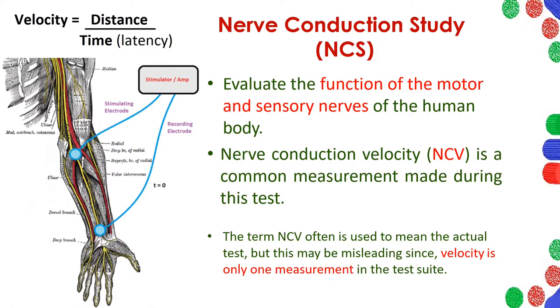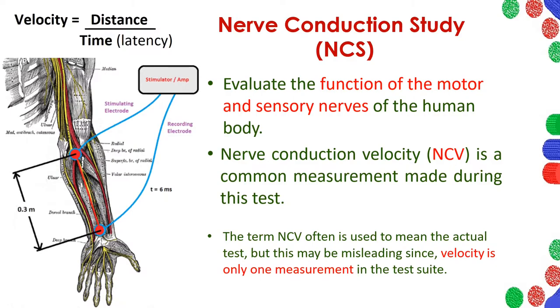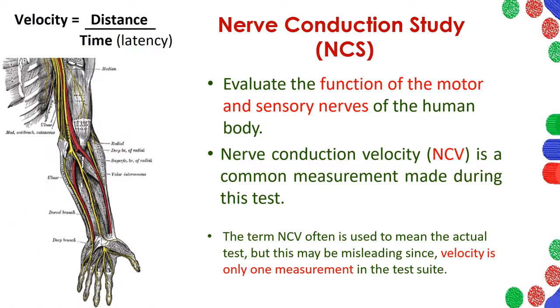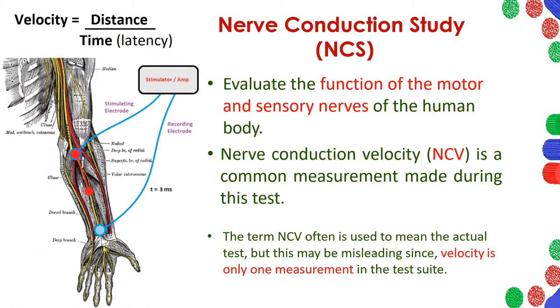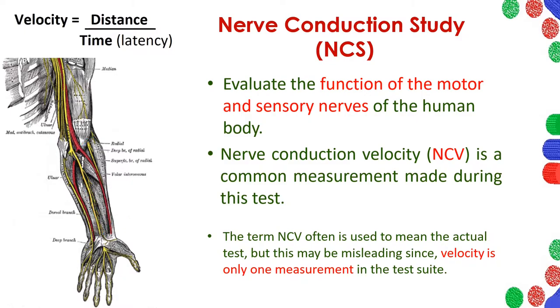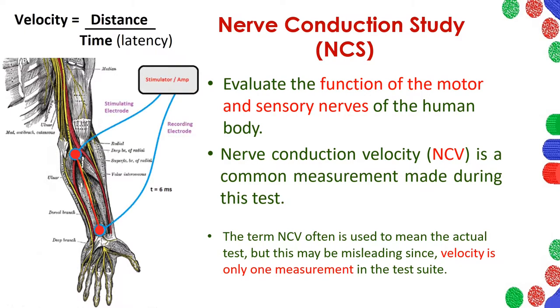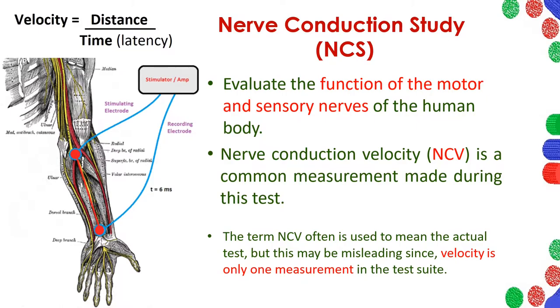To understand the principle of nerve conduction velocity, you have to go to physics where velocity is defined as distance upon time. Here the principle is also similar and very easy. What we do is stimulate one of the nerves with a stimulating electrode at one point. This impulse is created at this point and travels down the nerve. There is a recording electrode at another point, far away from the stimulating electrode. The distance between the stimulating electrode and the recording electrode is the distance, and the time taken for the impulse to travel between them is the time — known in medical terminology as latency. So we know the distance, we know the latency, and so we get the nerve conduction velocity.